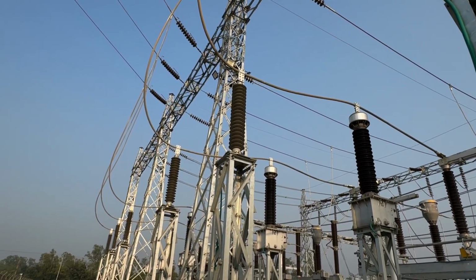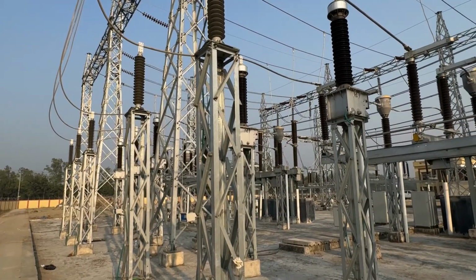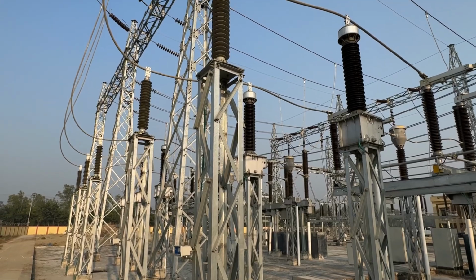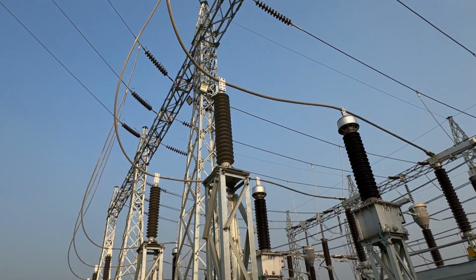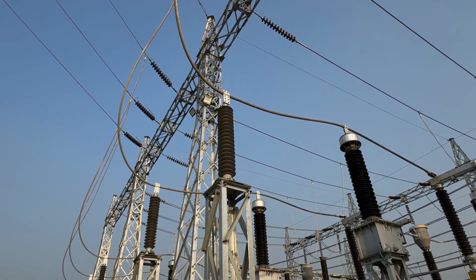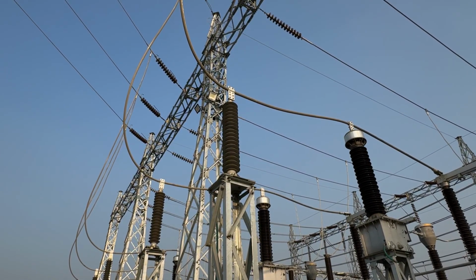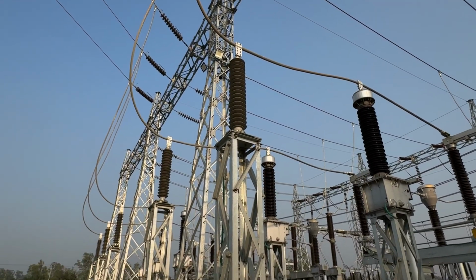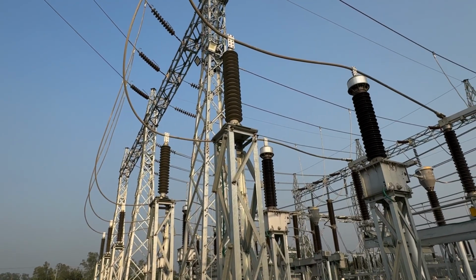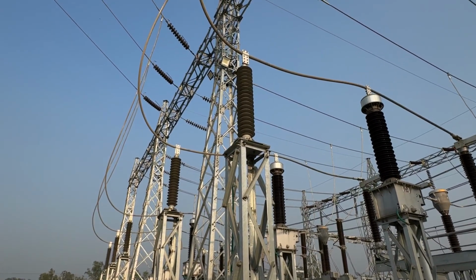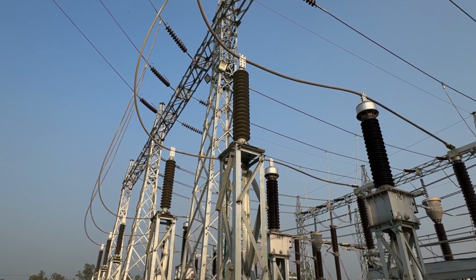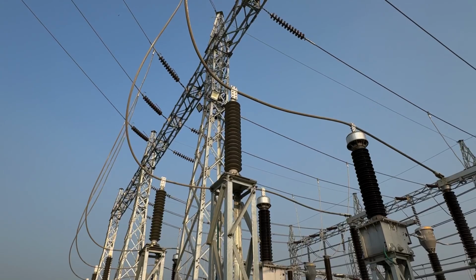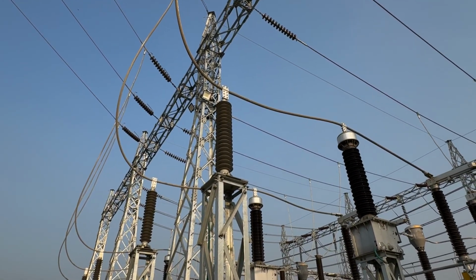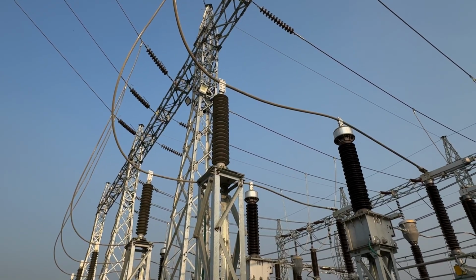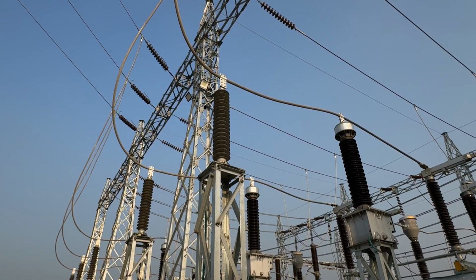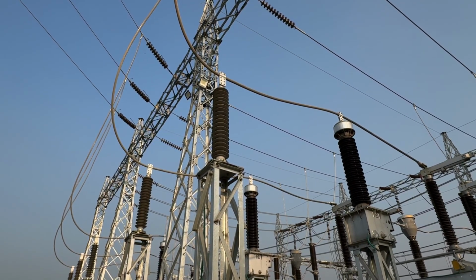What is the rating of this lightning arrestor? Normally, knowing that, we have to learn what the phase voltage of this 132 kV system is. It is approximately 74 to 75 kV. The rating of the lightning arrestor is calculated to be approximately 50 to 60% more than the system voltage. So it is 120 kV, a 120 kV arrestor connected with a 74 to 76 kV system.